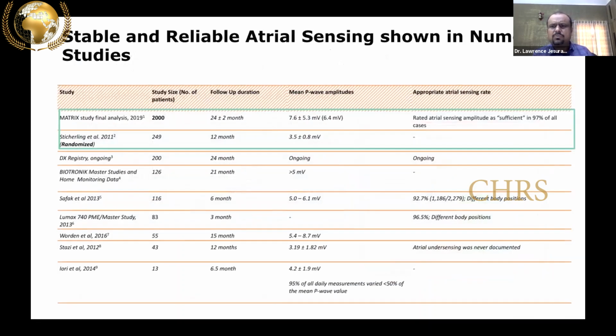One thing we were always worried about, from our experience from the pacemaker time, we have implanted a good number of pacemakers which have a VDD kind of a lead, but the problem was always in atrial sensing. Although the atrial lead during the implantation was in a good position, and you are sensing a good P wave, over a period of time there is a significant undersensing of the atrial channel. But the good thing about this particular lead and the devices, the atrial sensing is reliable over a long period of time. We have an experience of more than 1.5 to 2 years in our own patients who are doing extremely well.